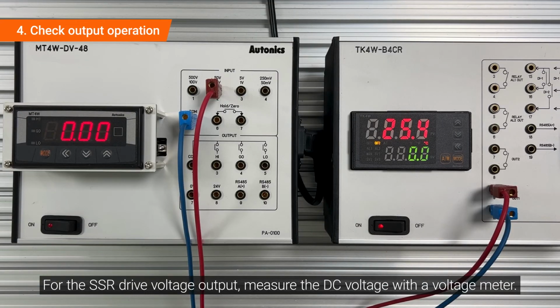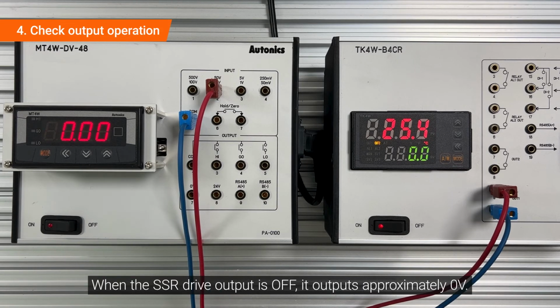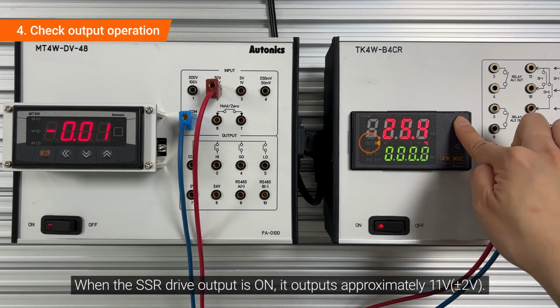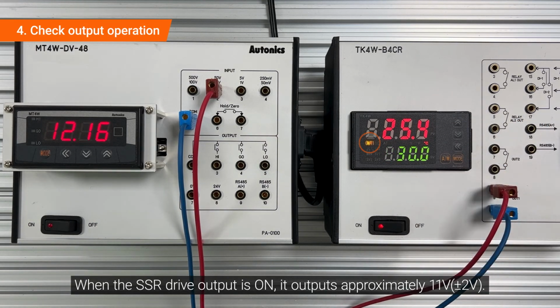For the SSR drive voltage output, measure the DC voltage with a voltage meter. When the SSR drive output is off, it outputs approximately 0 volt. When the SSR drive output is on, it outputs approximately 11 volt.